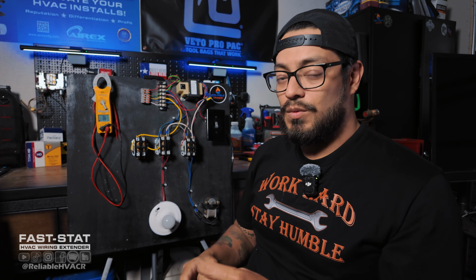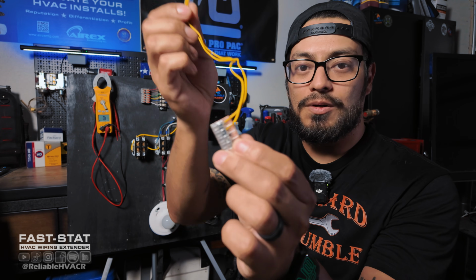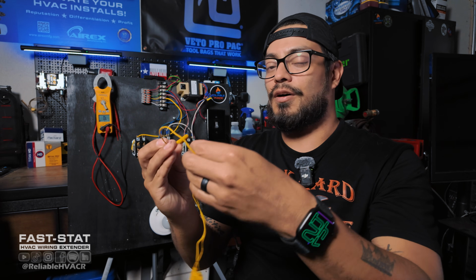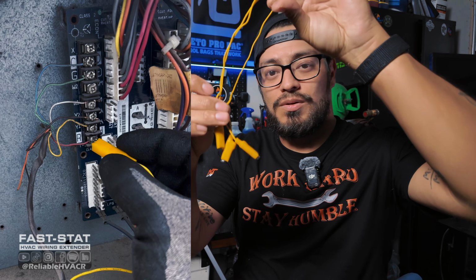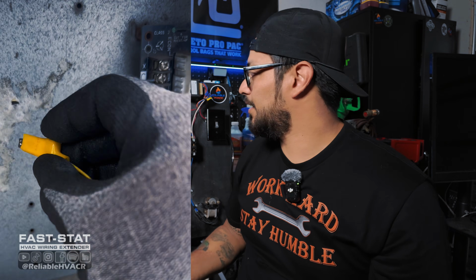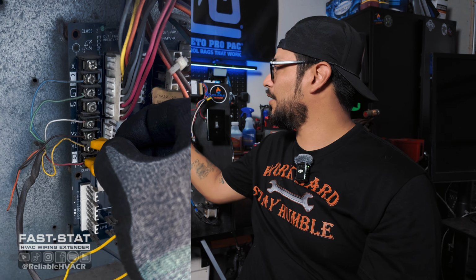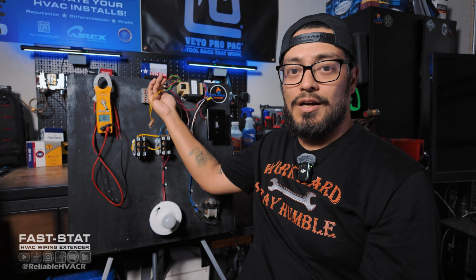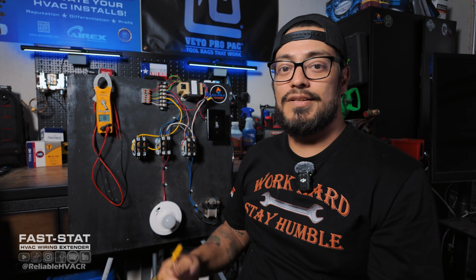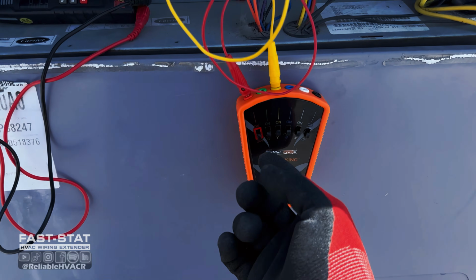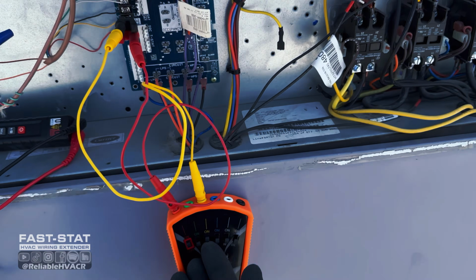If you're not sure that it's your thermostat and it doesn't take batteries, you need to check it with the faceplate off. You would make some jumpers. I have this one with a Wago clip. You can also use a wire nut, because I cut up several jumpers. That way I can call different stages of cooling and different things. So if I need to isolate and call for cooling, I would hook it up to R, and then I can hook it up to either green, yellow, Y1, Y2, whatever it is. So I can start making sure that it's not the thermostat. So if nothing ever pulls in and you're unsure, use a jumper. And if it still doesn't call, then obviously you might want to look for a broken wire or something that is tripped.